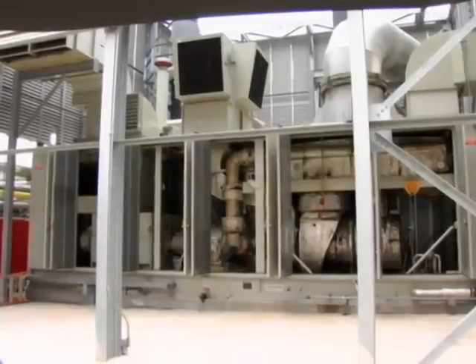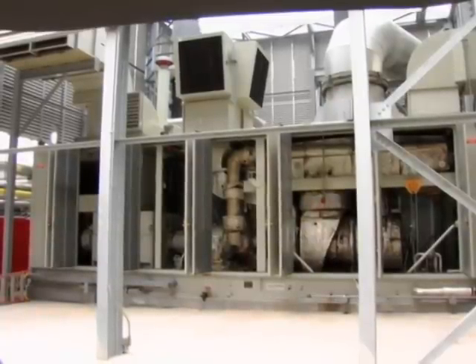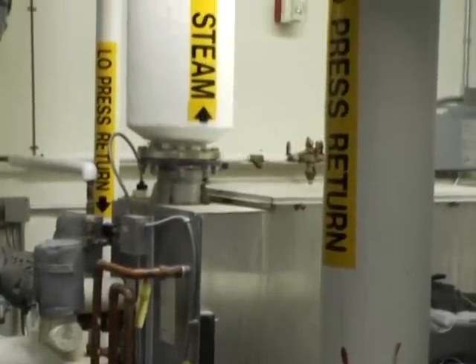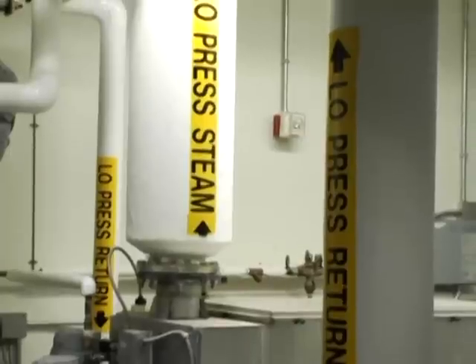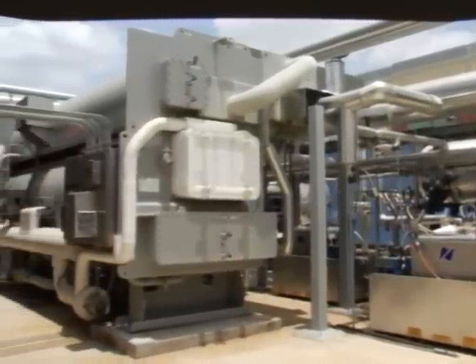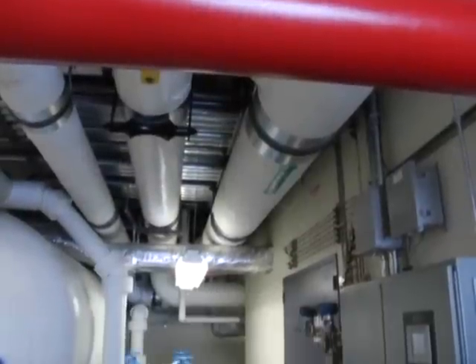Electricity is made from a natural gas-fired turbine directly coupled to a generator, producing about four megawatts. The exhaust heat from that gas turbine — approximately 850 degrees — goes to a heat recovery steam generator, making steam up to about 120 pounds. That steam is used to make hot water distributed throughout the hospital, and also for sterilization of surgical instruments using autoclaves. Additionally, steam that would normally go up a smokestack drives turbines into a thermal storage tank, where absorption chillers convert it into chilled water that goes directly to the hospital and into underground loops serving customers in the area.